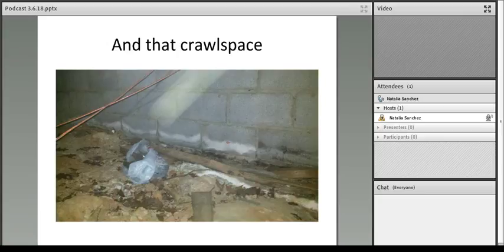So we have flood vents or something to relieve pressure, let water flow into the foundation. But if we don't have a vented crawl space by purpose - we have it vented because the old building code said we had to - we don't want vented crawl spaces. We like to think of crawl spaces as a basement I can't stand up in. Maybe I can't even kneel in the crawl space, it's so shallow, but I want that crawl space to be like a basement. No direct holes to outside, insulated on the sidewalls, and if I have ductwork, I want that ductwork back inside the house. So I've got to go in my crawl space and check it out.